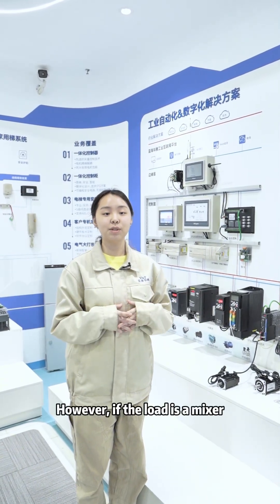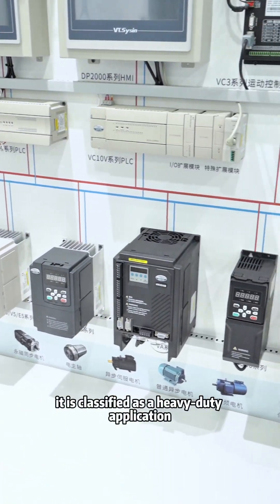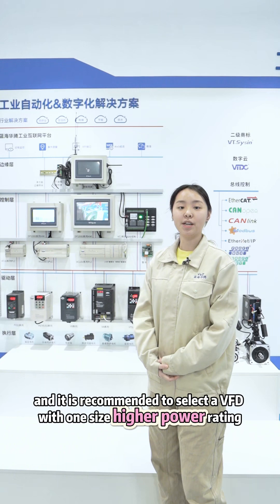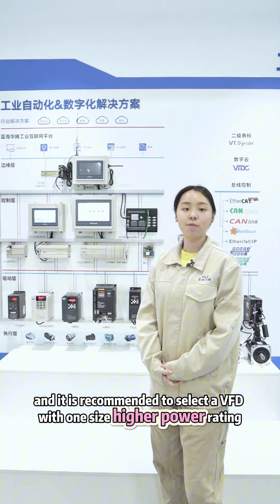However, if the load is a mixer, it is classified as a heavy duty application, and it is recommended to select a VFD with one size higher power rating.